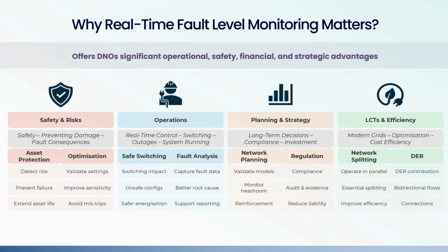Now, stepping into the planning and strategy view, traditionally, fault level studies are snapshots. They tell us what might happen, but with real-time monitoring, we turn this into a continuous picture of what actually happens on the network. It allows planning models to be checked against real network behavior and highlights where fault headroom is being eroded over time. And this basically means that reinforcement is targeted only when it's needed. At the same time, it gives us some auditable evidence for compliance, supporting our reporting and confidence in our long-term investment decisions.